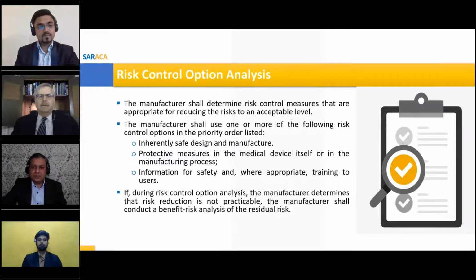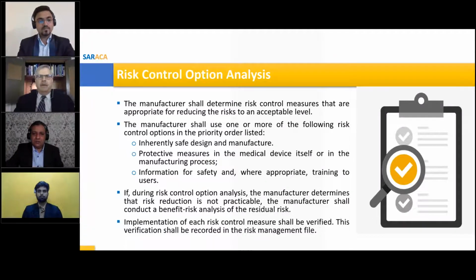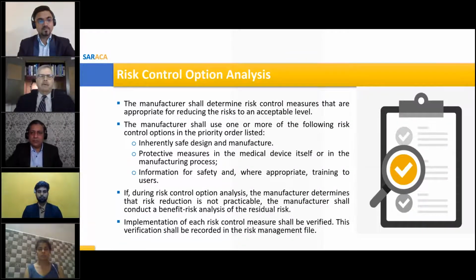And the next part of your process is to ensure that when you're manufacturing that device or IVD or whatever the product is, that you manufacture it in a safe way or a way that will mitigate any risk that may or may not be identified as part of your process. For example, your wiring harnesses on an electromechanical device, are they held in place? Do they take sharp corners? Do they go through areas that have, for example, a hole in one wall? Do they go through that hole and can rub back and forth and eventually cause a hazard? Do you have enclosures over moving parts that will reduce the risk of an operator putting their fingers or hands or arms into that device and incurring harm?